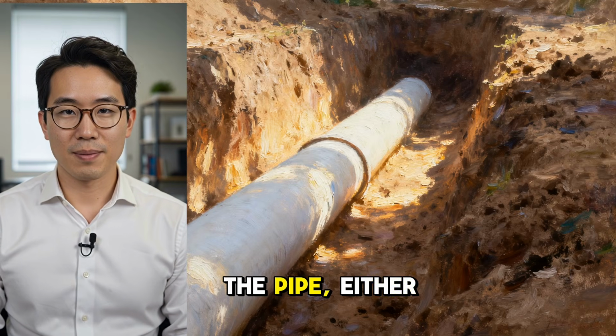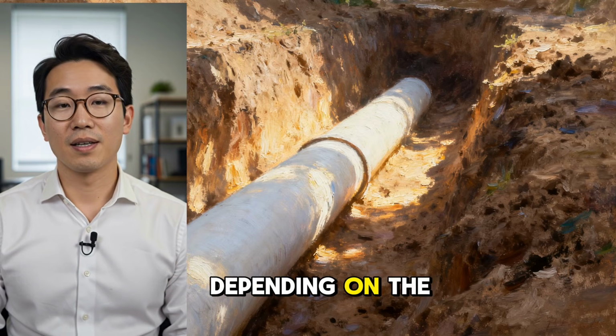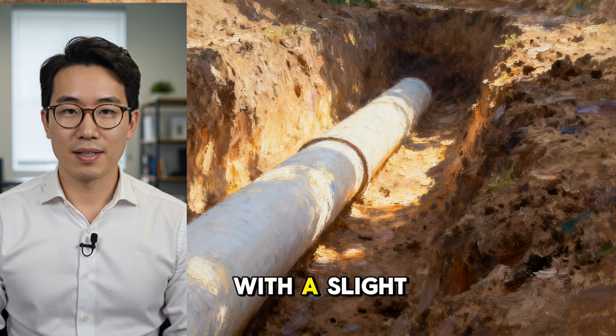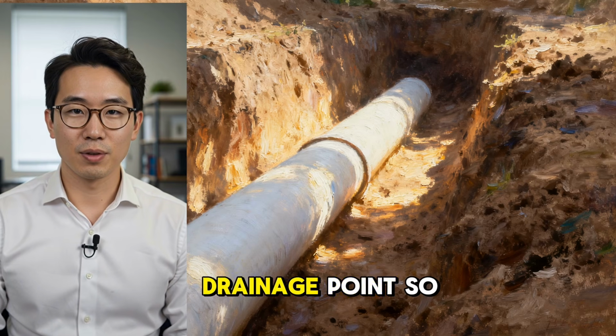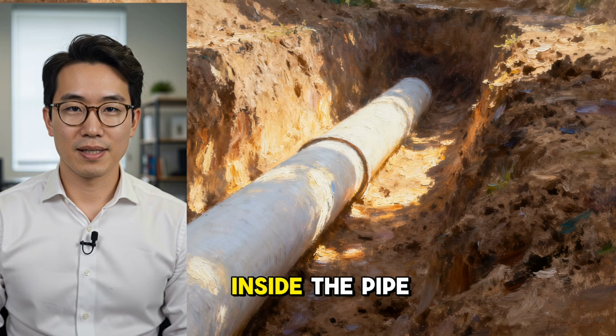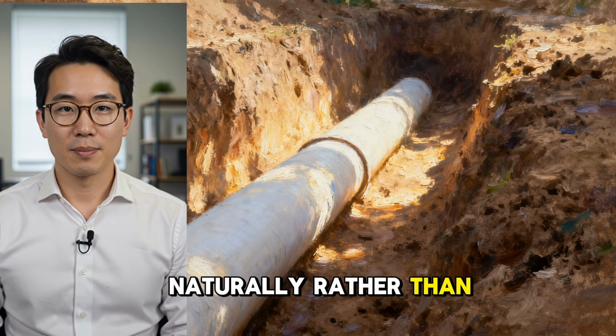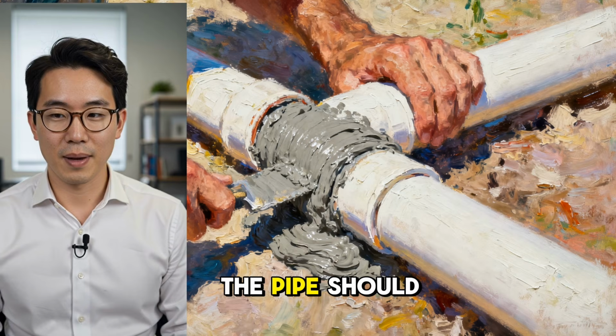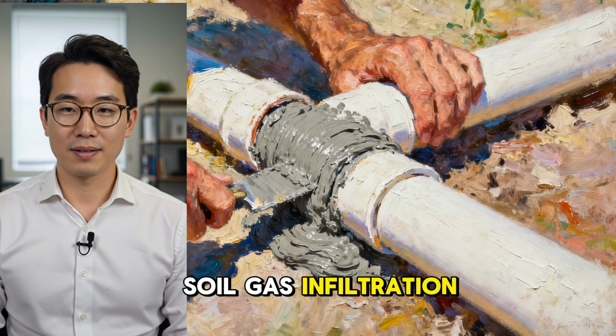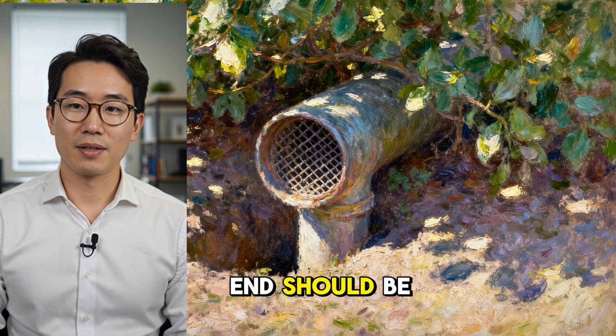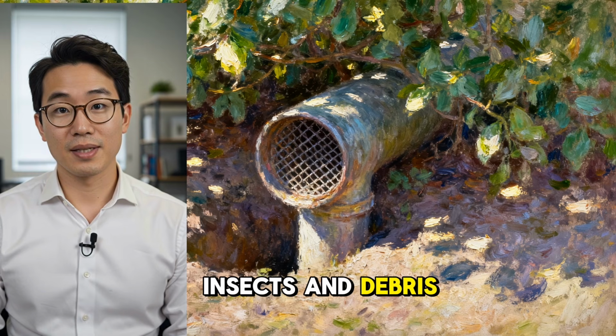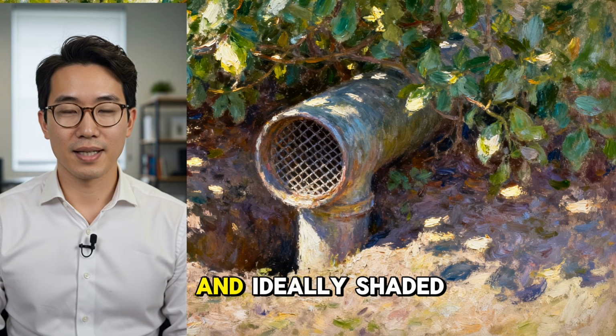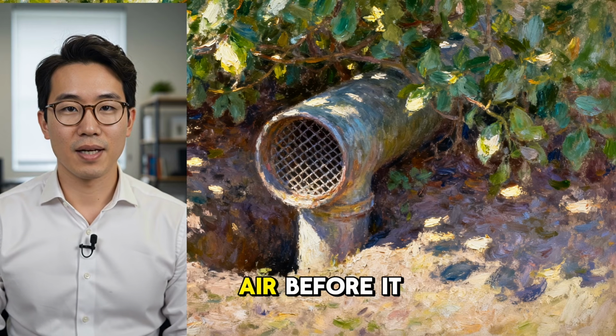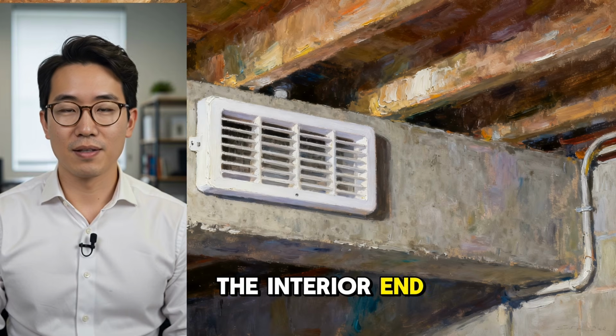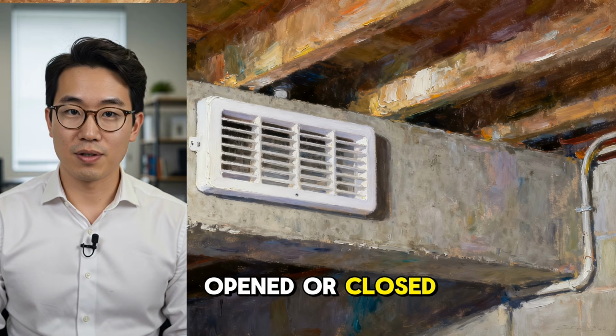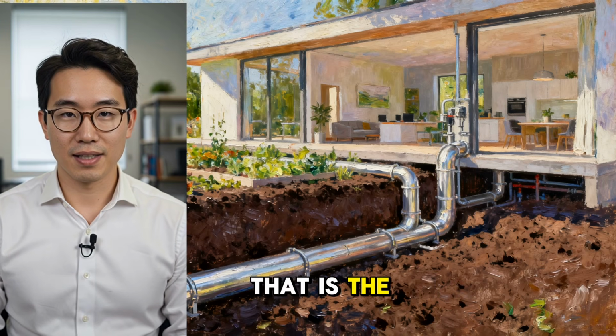The pipe, either 4-inch or 6-inch diameter depending on the desired airflow volume, should be laid with a slight slope toward the exterior or toward a low drainage point, so that any condensation that forms inside the pipe can drain out naturally, rather than pooling and creating moisture problems. The pipe should be sealed at all joints to prevent soil gas infiltration. The exterior intake end should be fitted with a screen to exclude insects and debris, positioned away from sources of polluted air, and ideally shaded to prevent preheating the incoming air before it even enters the system. The interior end should connect to a simple vent that can be opened or closed depending on whether cooling is desired. That is the complete system.